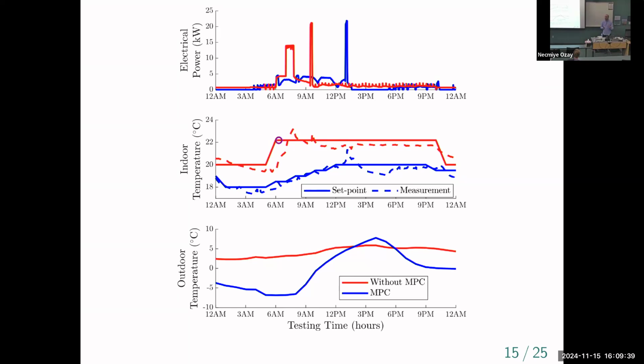It thinks that it has run out of thermal capacity, and it says, oh no, we need to turn on this backup electric resistance heating element in order to keep the house warm. And so for that reason, we see a spike in electric power usage in the morning with a bit of a time shift, basically because of the delays built into the manufacturer controls.